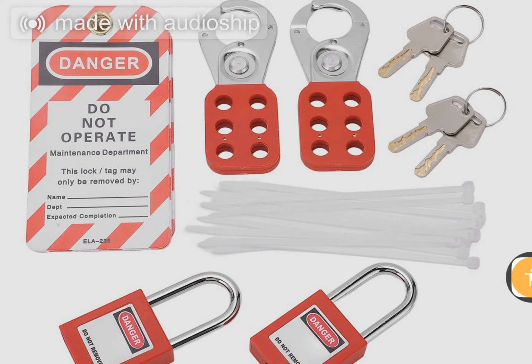And finally, step 6, verification. Which brings us full circle. You use a tested, proven voltage detector. Following our 3-point test, of course. Following the 3-point test, you verify the equipment is definitively de-energized. Only then is it safe to work.